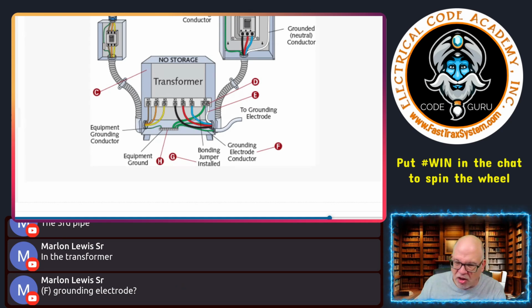Yes. In the transformer, yes, as long as this system bonding jumper is of the wire type or of the bus bar type and it is adequately or properly sized, then yes, just like it's shown here, you could take this over and connect it to this equipment bus right here. Perfectly acceptable, because this is adequately sized. Is that answering your question? Thought I answered that question.